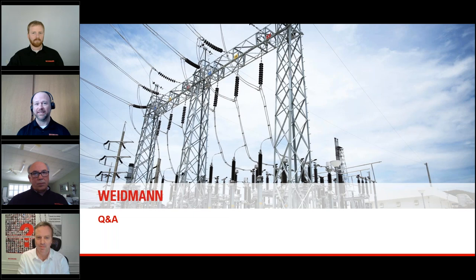Thanks, Jason. How prevalent is methanol assessment with regards to determining paper life expectancy? I'll take that one. If you're looking at a transformer that's in service, we try to measure the insulation life by this degree of polymerization that I described earlier. The challenge is that if you have a transformer in service, you're not able to get a sample of the paper pressboard from the location that you want to test to do this viscosity measurement.